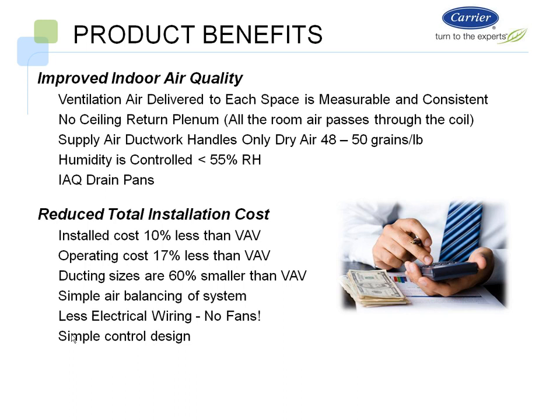Typically, in a sensible only system, you would also probably over-ventilate because you're over-designing in that space, where here you don't have to. And there's only a couple methods that would ensure it. In a VAV system, you'd either have to put CO2 sensors in every space or zone, and/or have an airflow station in your air source, and it still doesn't guarantee that that's getting to the space. For this, it's in the space, and that is the only air that's actually being introduced in these spaces. Supply air duct, again, is going to be cleaner because you're handling drier air typically, and your humidity is always controlled at 55 or less. Again, as we said, if you wanted antimicrobial, we can provide that in our drain pans.